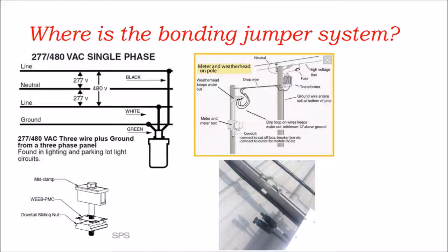different requirements for when you're under 250 volts and over 250 volts. But basically, when we're talking about solar power and on-site energy management systems, you need to ground all metal parts, and you'll make mistakes when metal parts that you think don't need to be grounded do actually need to be grounded. All your metal parts and your battery systems, etc., need to be grounded.